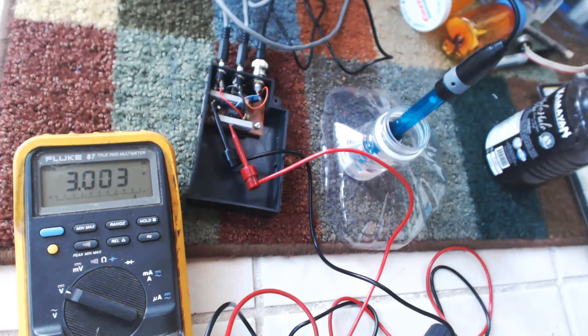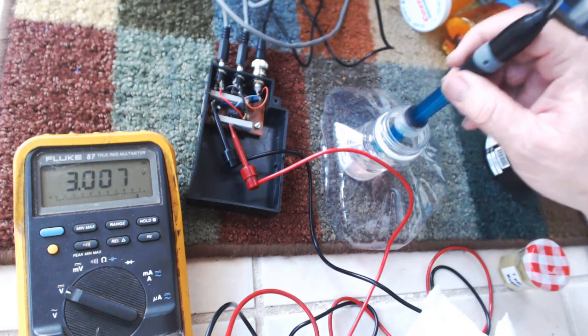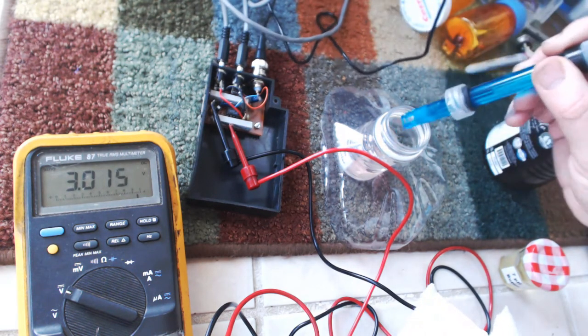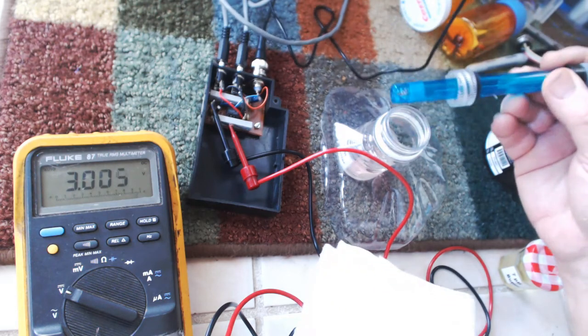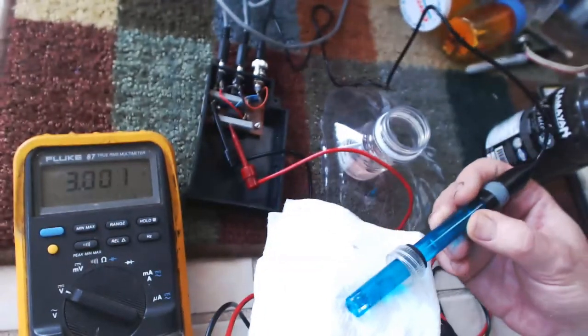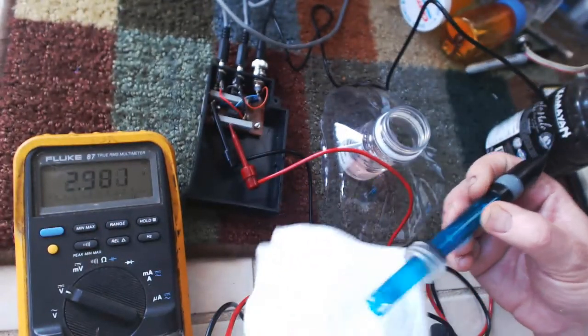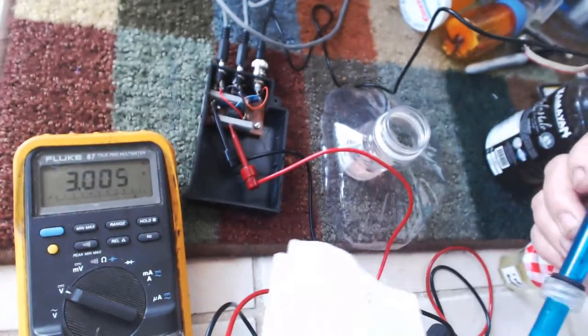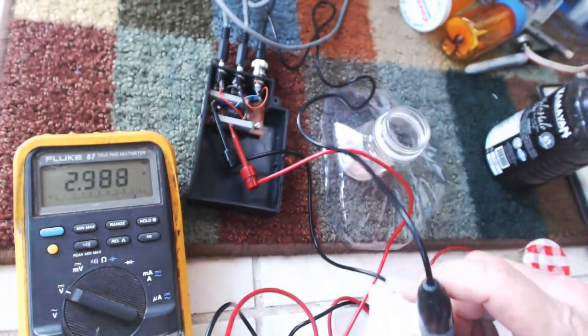Now that's what I was looking to see, a reading of about 3 volts. It's going to bump around a little bit. I find it's a little more stable on the top end than on the bottom end. Now it's time to prepare the probe to actually test the sample. Again, same routine: get as much solution off as you can, then dab off the outside of the probe with a paper towel, making sure I don't contaminate my sample.